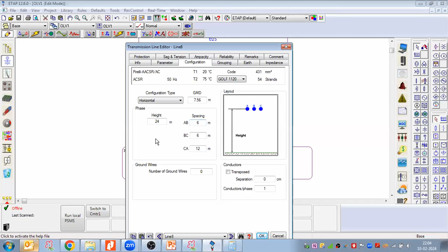A, B, C represent R, Y, B phases, so R to Y and Y to B indicate the spacing between phase conductors. I'm taking 6 meters as an example, which is typical for 400 kV lines. Then, looking at resistance, you can see a default calculated value based on these parameters and configuration—this impedance is taken here. Alternatively, we can click user defined and put in the real value directly.